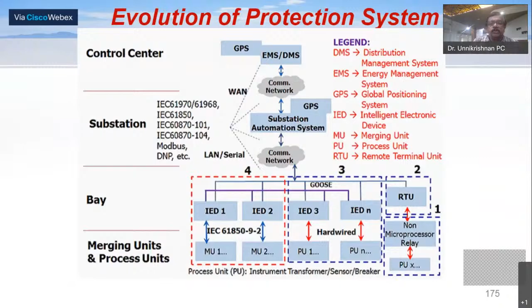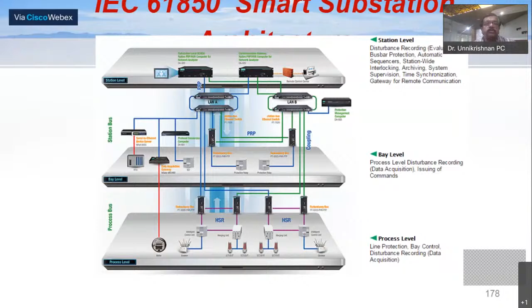Let us see what IEC 61850 protocol is. Here, the entire substation is divided into 3 layers: the process layer, the bay layer, and the station layer. All line protection devices and disturbance recording devices are in the process level. Recording and issuing of commands to the process level is done at the bay level. At the station level, higher functions like supervisory control and synchronization are performed. This is again an elaboration of the 3 levels: process level, bay level, station level.